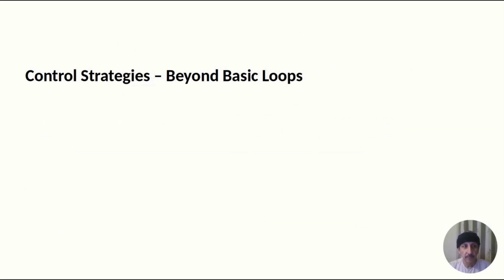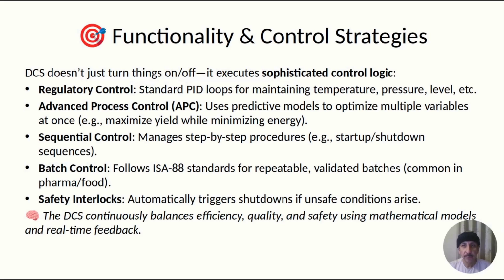Control strategies, beyond basic loops. DCS goes far beyond simple on-off logic. At the base level, it runs PID loops, which are proportional integral derivative control, to maintain variables like temperature or flow. But modern DCS also supports advanced process control, APC, which uses mathematical models to optimize entire units.